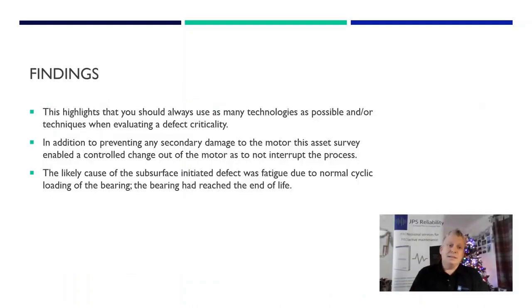So the summary of the findings: don't just use one technology within vibration, use all the technologies. Use your eyes, strip the bearing down, look at it, look at the lubes, look at the oils. And this type of action does prevent any secondary damage. And one key thing is, we've proven that there's an electrical defect and electrical noise was killing the grease, but you mustn't forget all that electrical harmonics is also killing the insulation on your windings. So it's a bigger thing than just bearing health. It's whole motor reliability, which, as I said, we work on with Mark Gurney from PHY in the motor reliability sector.